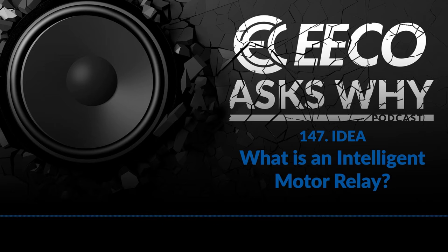So we're going to talk about intelligent relays today, and maybe to get us started, we can give our listeners a little bit of insight about some of the typical motor failures that industrial end users see on a regular basis that these relays could help with. Any general failure — you have common ones commonly referred to as somebody let the smoke out of the motor. What gets lost in considering some of the new technologies wrapped around intelligent relays is that any condition a motor is exposed to, whether mechanical or electrical failure, even in its early stages, can be expressed in the consumption of current and voltage by that motor. That's really the basics of intelligent relays and their ability to provide advanced protection.